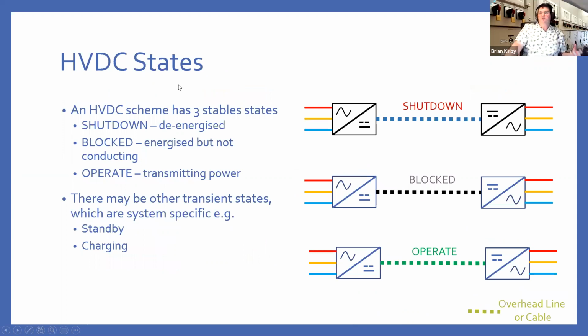So an HVDC system, if we look primarily at a point-to-point system, it normally has 3 stable states. It can be shutdown, so there's no energy in the system at all. It can be in what's called a block state, where your converter stations are energized, but there's no flow between them. And then it can be in the operate state, where there's energy flowing from one side to the other. You may have other transient states within the system, standby, charging, etc. But these are all transient, as the name suggests, where you're transitioning from one stable state to another.